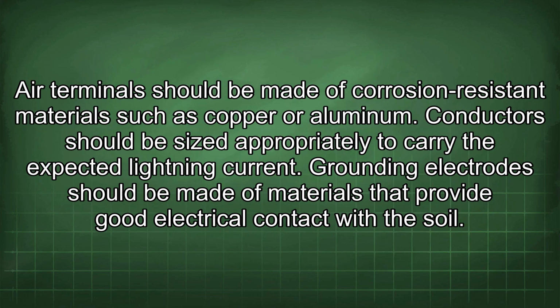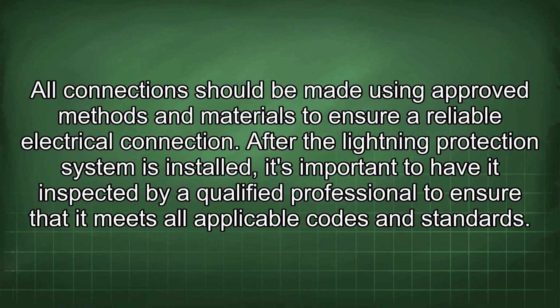Air terminals should be made of corrosion-resistant materials such as copper or aluminum. Conductors should be sized appropriately to carry the expected lightning current. Grounding electrodes should be made of materials that provide good electrical contact with the soil. All connections should be made using approved methods and materials to ensure a reliable electrical connection. After the lightning protection system is installed, it's important to have it inspected by a qualified professional to ensure that it meets all applicable codes and standards.